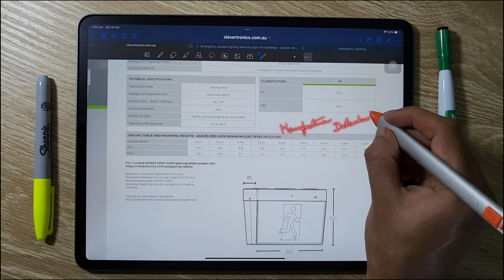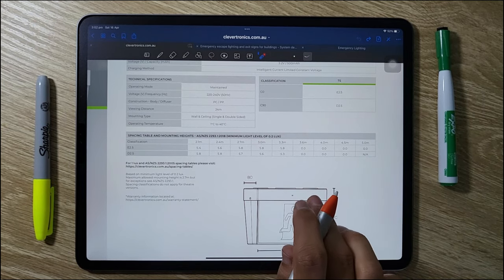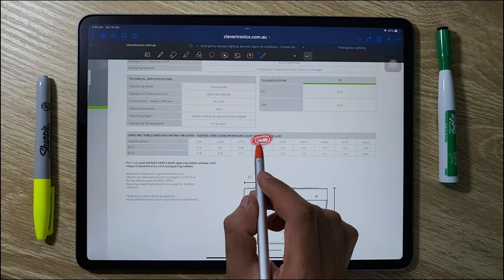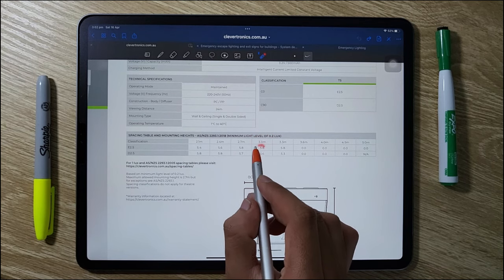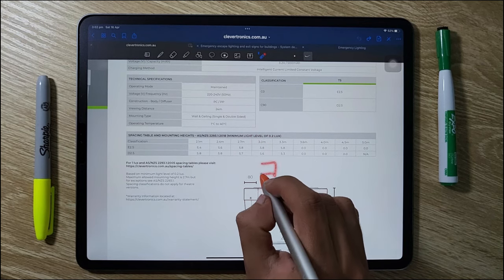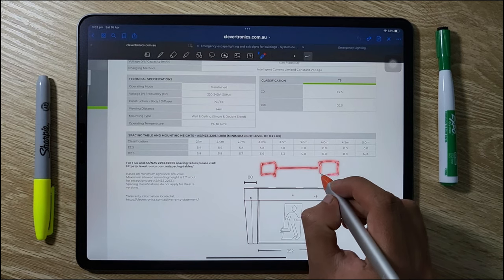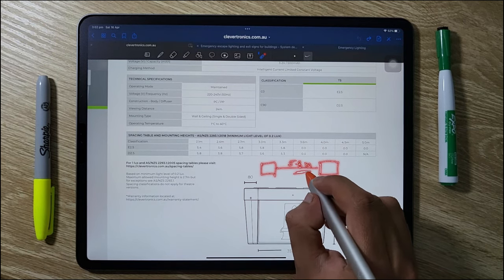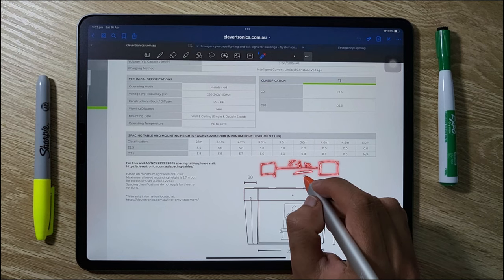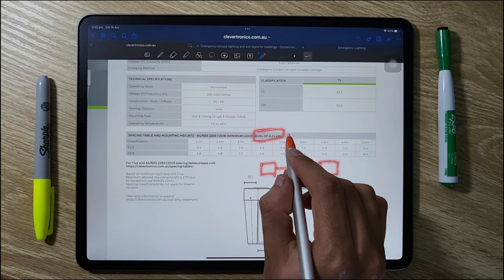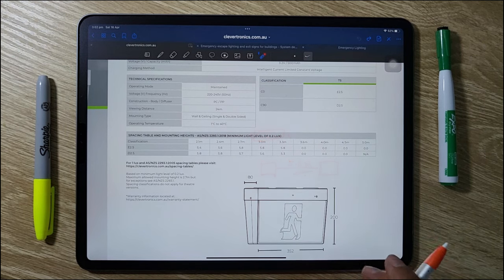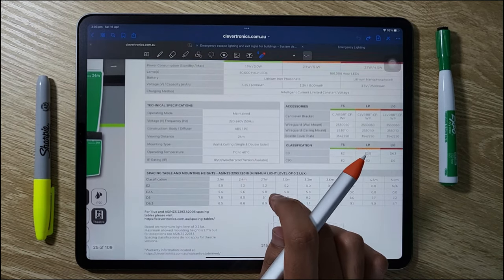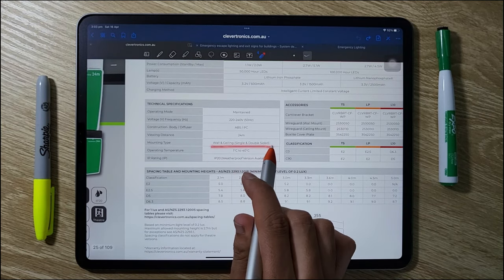The manufacturer data sheet will give information about spacing between the emergency light and the emergency exit sign, as well as the mounting height. The mounting height should not be more than 2.7 meters. In our project the ceiling height is 3 meters, but we consider 2.7 meters as the maximum mounting height, so the distance between the emergency light and emergency exit sign should be not more than 5.7 or 5.8 meters as per the table. I'm going to use the Clevertronics exit sign for our restaurant project.